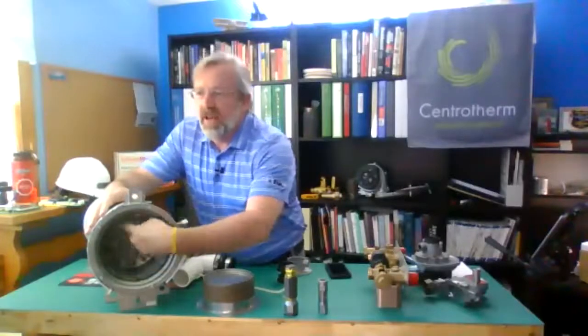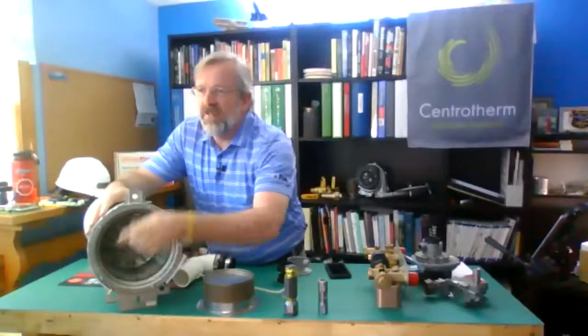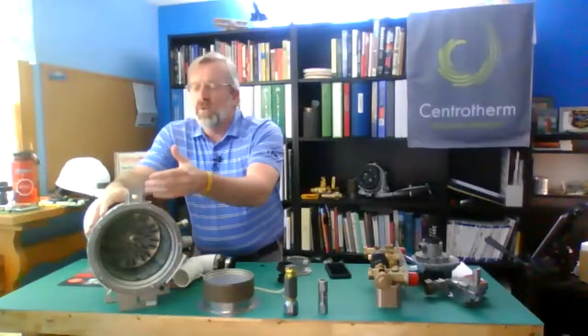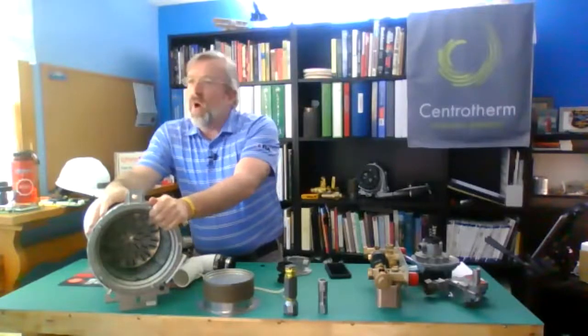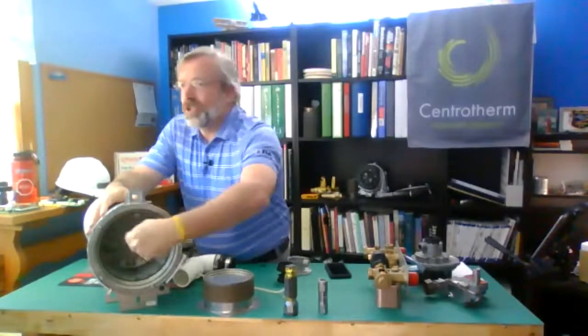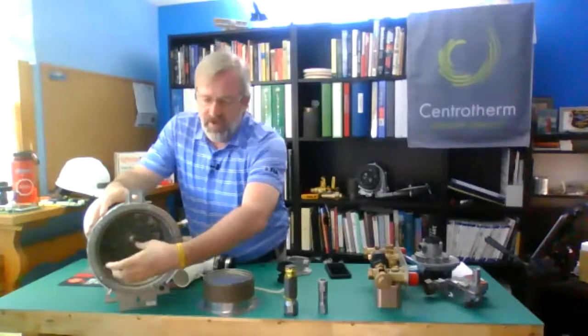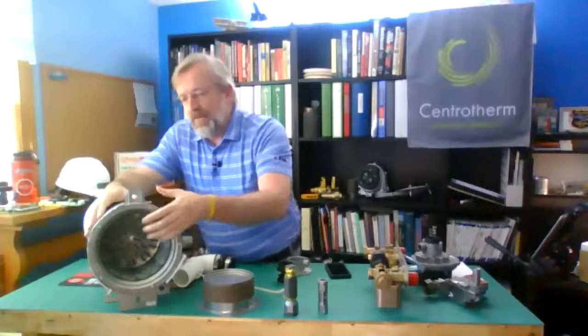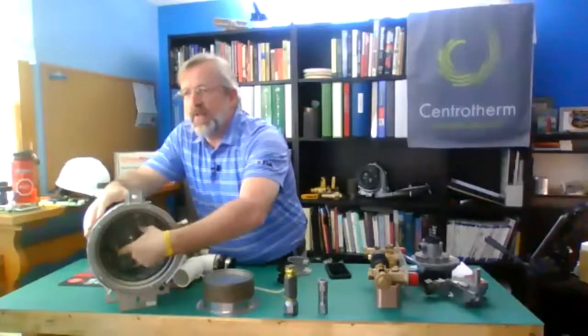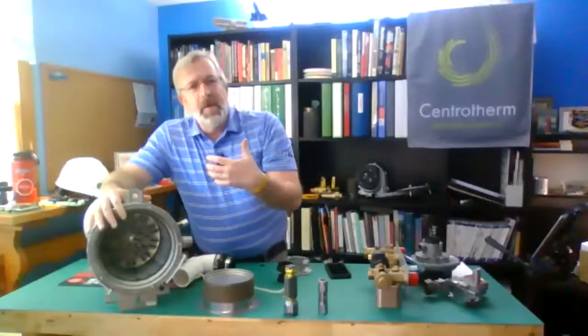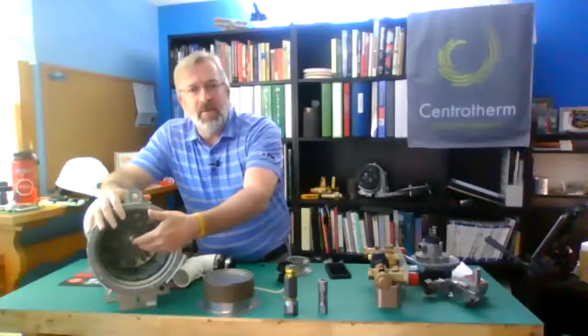Now, once I get it open, you guys can look down here in the fire tubes. That's what these openings are. When we talk about the water tube style boilers, we want to scrub those out and vacuum them. With the fire tube, it's a little different. If you have some leftover products of combustion in here, like coffee grounds, which we don't really see a lot, but if you do, vacuum them out.